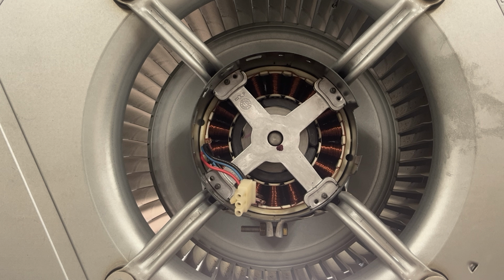If you are confused, you can easily tell if you have a motor that's bad or not. Because if I had a bad motor, a bad winding, guess what? It's not going to stop. It's just going to continue to spin because I won't have resistance. That's called the brake test.